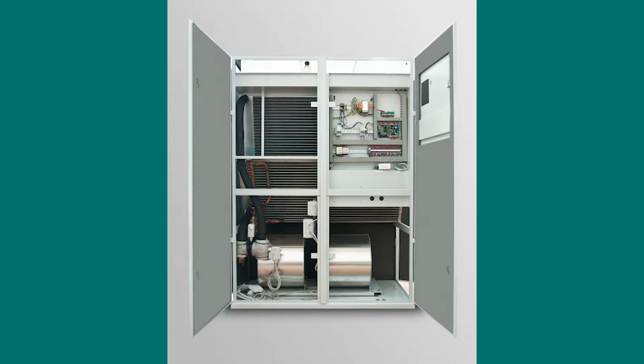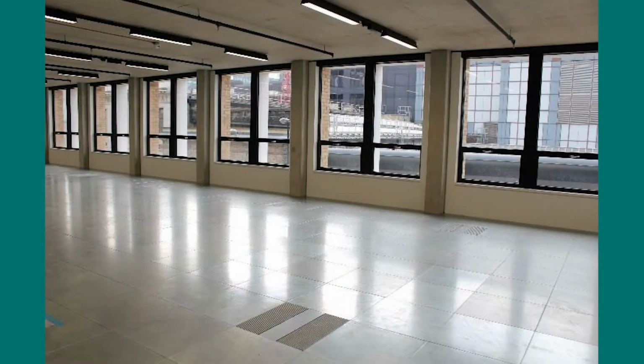An underfloor air conditioning system uses the few inches of space beneath a raised access floor to create the air ventilation path, eliminating the need for ductwork and piping. Underfloor air conditioning enables savings in construction materials, installation costs, fit-out and reconfiguration costs. In new build construction, it can free up additional lettable space or reduce overall building height. Notably for this project, it allows for more room overhead, an average usable space saving of 15%.